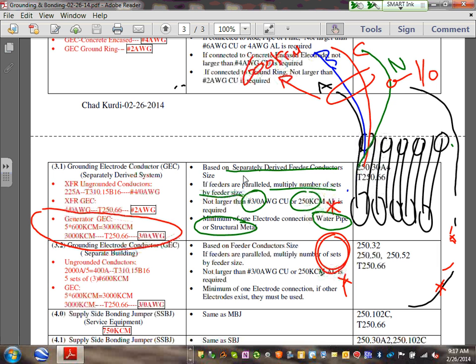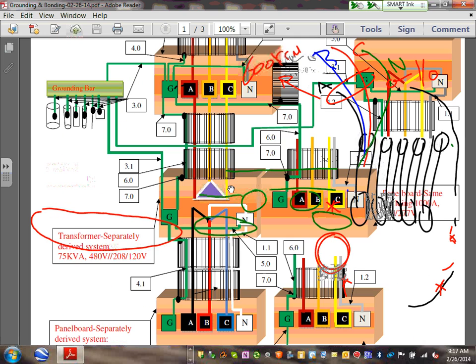Typically, guys, inside an electrical room like ours, which is going to be right in here, you will have a bus bar on the wall, and you tie all these grounding electrode conductors to it. Any comments, guys? Any questions? So what you have witnessed is grounding and bonding, gentlemen, for multiple things.